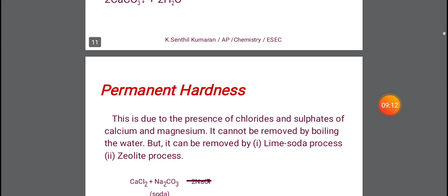Then go to the permanent hardness. Permanent hardness is due to the presence of chlorides and sulfates of calcium and magnesium. That means calcium chloride, magnesium chloride, calcium sulfate, magnesium sulfate. So these are some of the permanent hardness producing salts. It cannot be removed by boiling the water, but it can be removed by two processes.